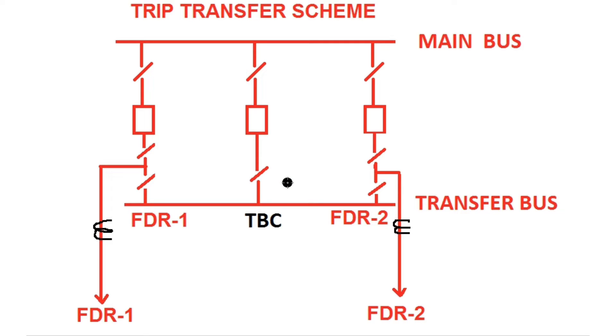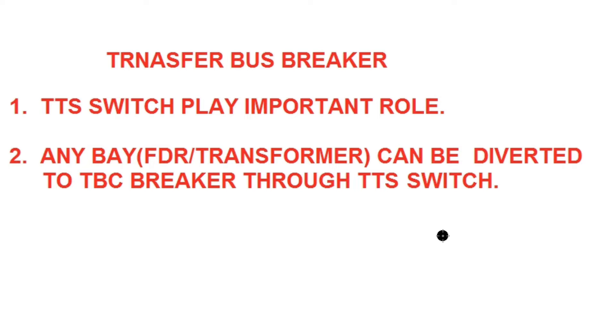In this video I will discuss about what is the trip transfer scheme and how the trip is transferred to the transfer bus coupler breaker. In case of the trip transfer scheme, the TTS switch — that is the trip transfer switch — is connected in each feeder panel or transfer panel. The TTS switch plays an important role for the trip transfer scheme, and in the TTS switch there is a normal, inter, and transfer position.